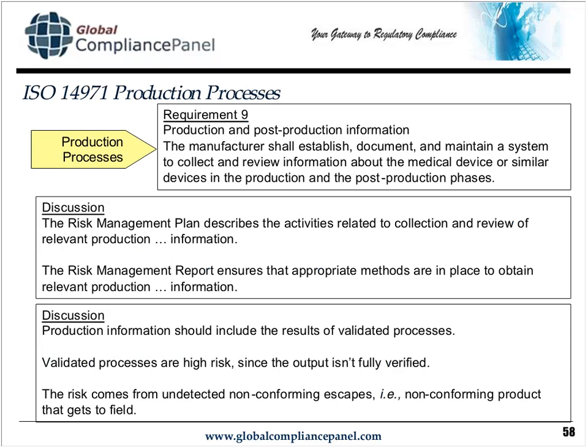Now, there's a requirement in 14971 that I have to collect and evaluate production and post-production information. And it's production information that I'm interested in here, because if I have a validated process and it has a risk associated with the process output, then I want to control that risk through process validation on the production floor. And so the risk management plan is going to tell me what information I'm going to collect and how I'm going to collect it. And so the idea here is that if I am controlling risk that might result from a process that requires validation or for which I've chosen to do validation, then I need to be collecting and evaluating that information as part of risk management.